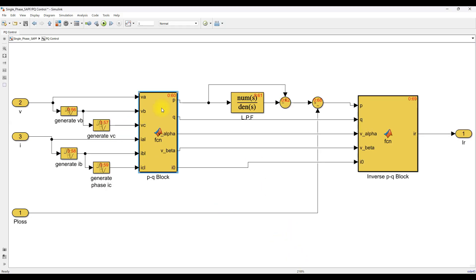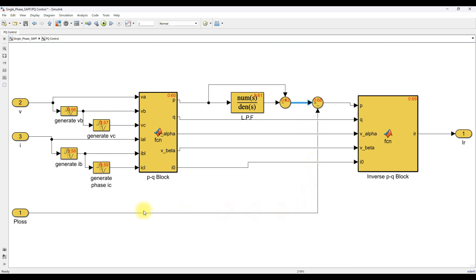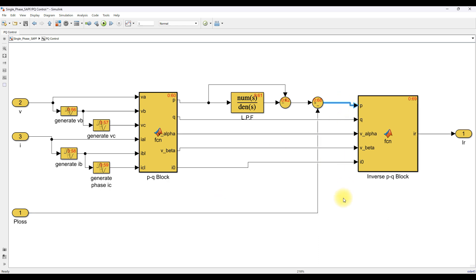Next, we take the real power and apply a low-pass filter to obtain the average value of the real power, filtering out the oscillating component. The filtered real power output is compared with the loss power from the PI controller to get the final real power reference. The reactive power is also extracted from the system — this is the reactive power we need to compensate in the AC source current, and it will be supplied from the shunt active filter.